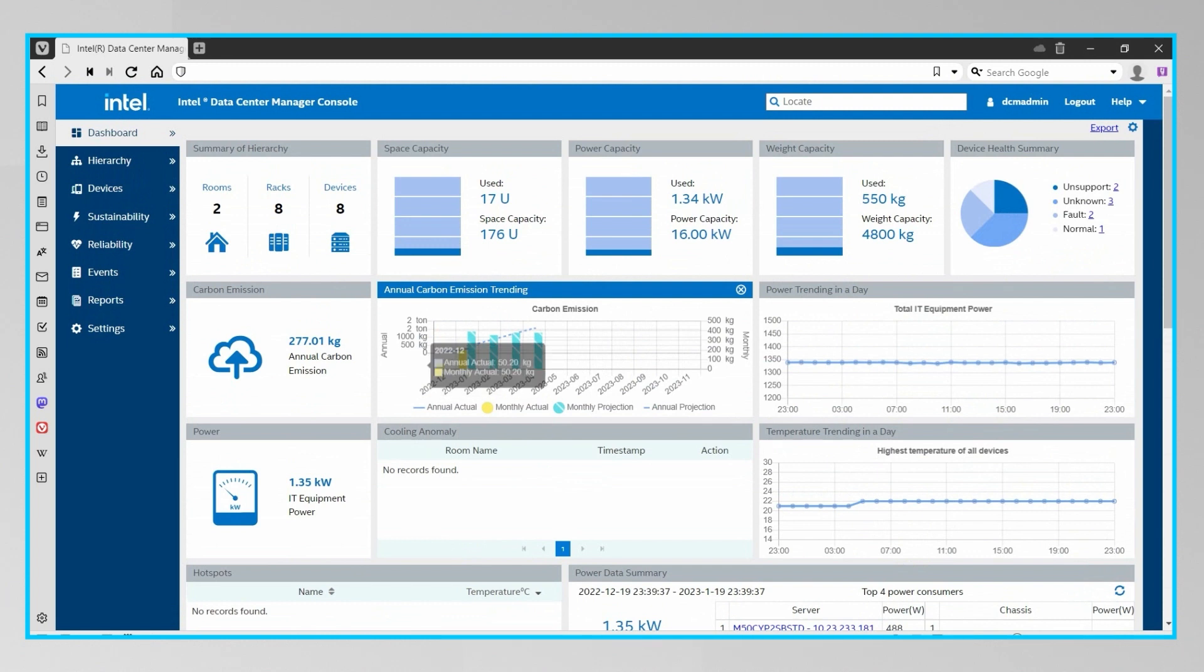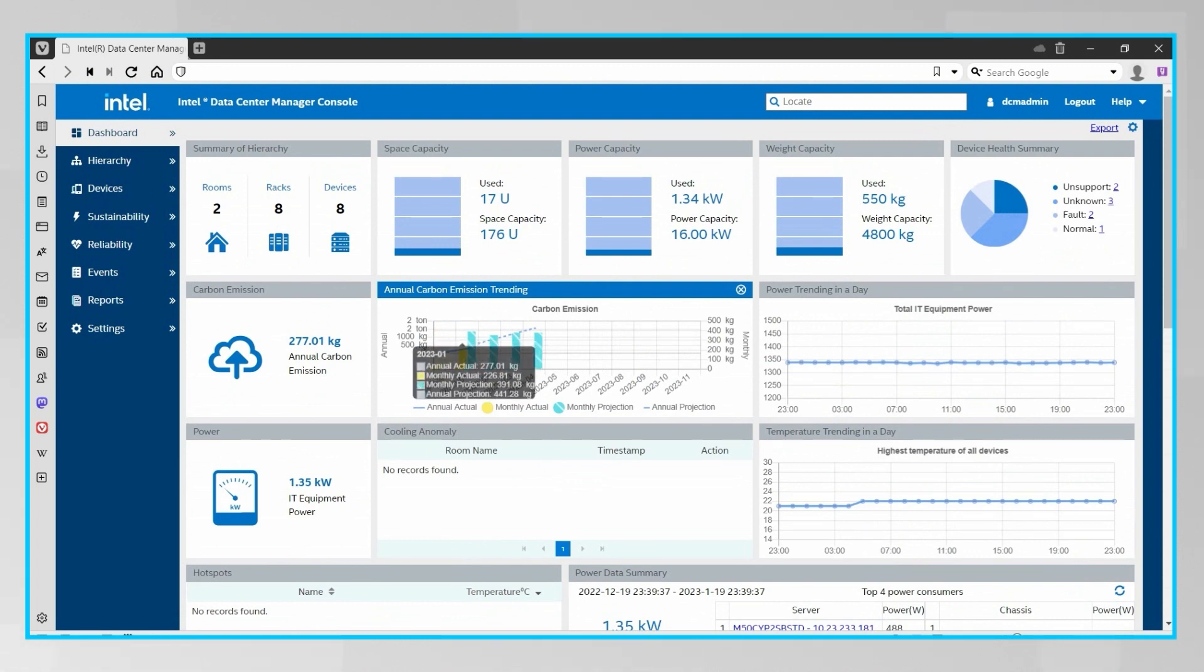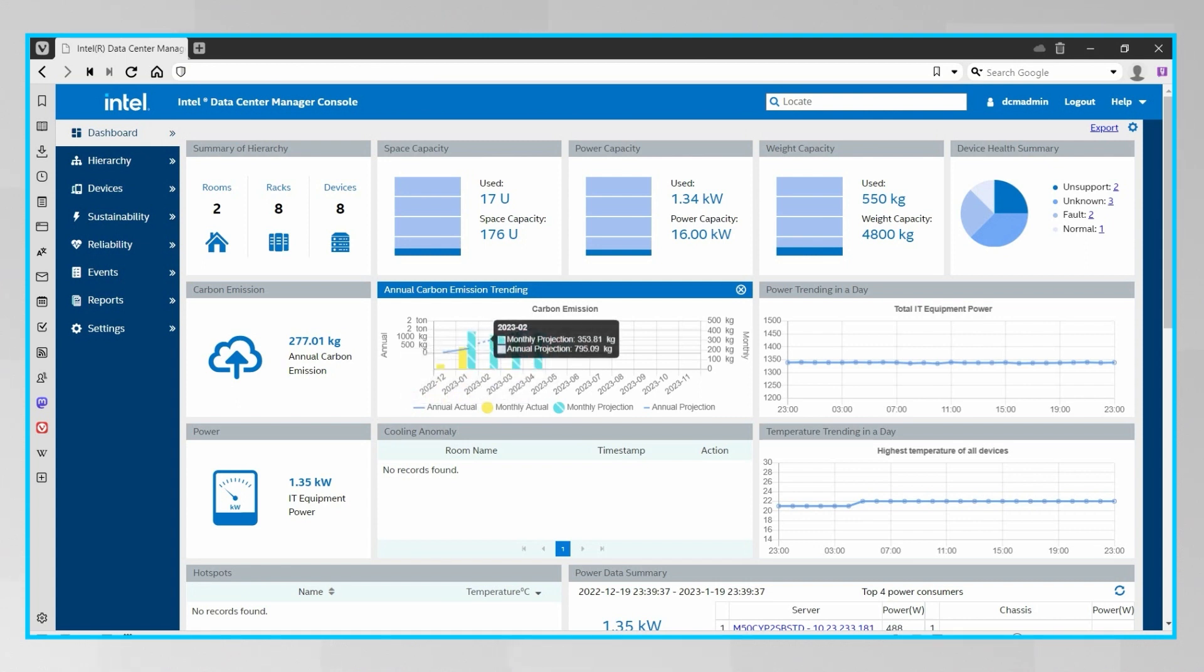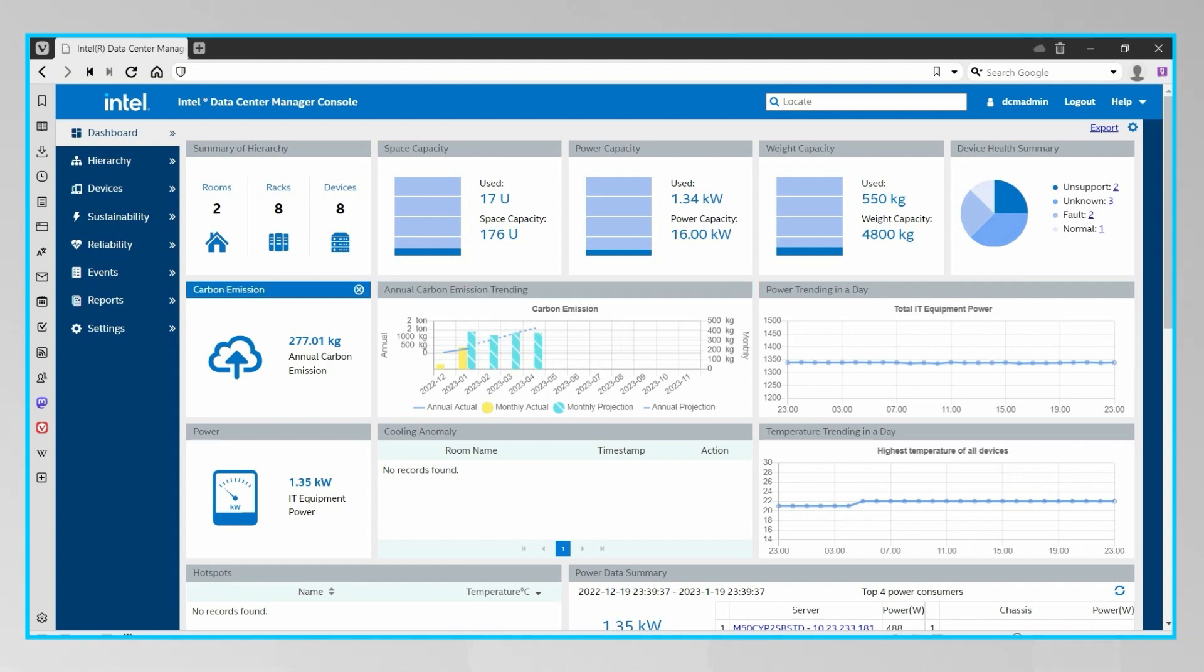The carbon emissions of a device is calculated based on the power consumption of that device, which Intel DCM monitors in real time, the data center's known PUE, or power usage effectiveness, and the carbon intensity, which is a measure of the amount of carbon dioxide or other greenhouse gases that are emitted per unit energy consumed, which is typically expressed in kilograms of CO2 per kilowatt hour.